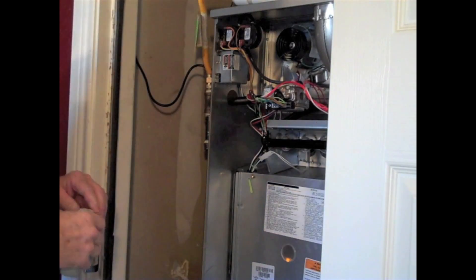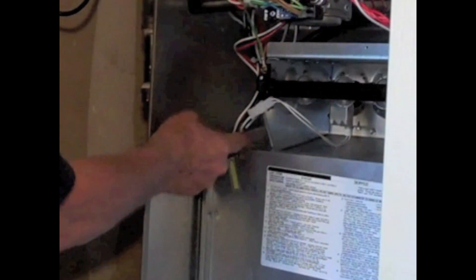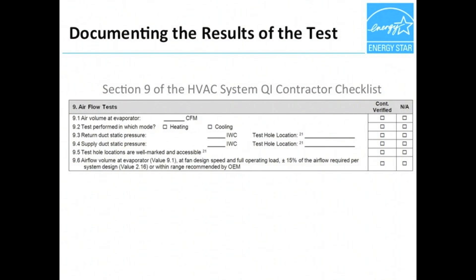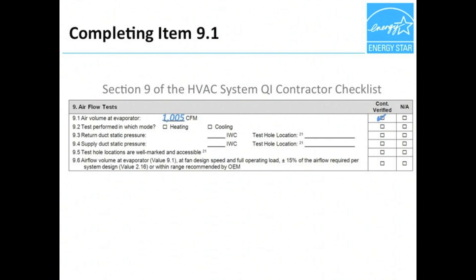Rob now removes the probes and plugs the holes with a plug, foil tape, or in the case of wire penetrations, a non-permanent putty. Now Rob can complete Section 9 of the checklist. In item 9.1, he records that the air volume of the evaporator was 1005 CFM. In item 9.2, he records that the test was conducted in cooling mode, which will help the rater duplicate this test in the same conditions. In items 9.3 and 9.4, he records the static pressure in the supply duct and return duct, and provides a general description of the location of each hole, such as "left top of cabinet," to help the rater locate these holes. In item 9.5, he checks the box to confirm that the test hole locations are well marked and accessible. Finally, in item 9.6, he confirms that the airflow volume reported in item 9.1 is within 15% of the designed airflow reported in item 2.16.